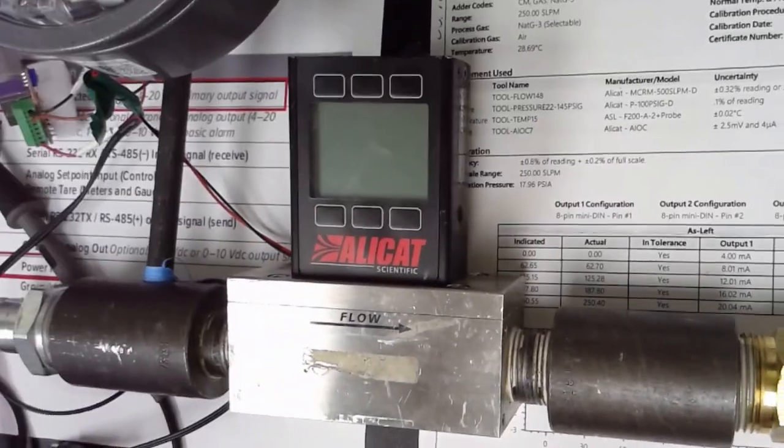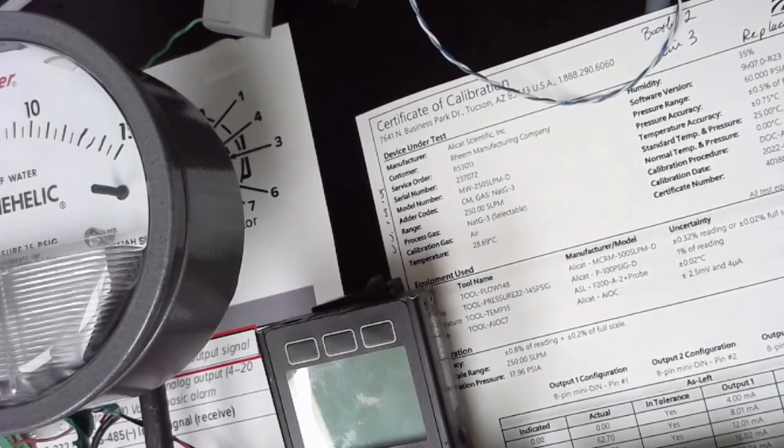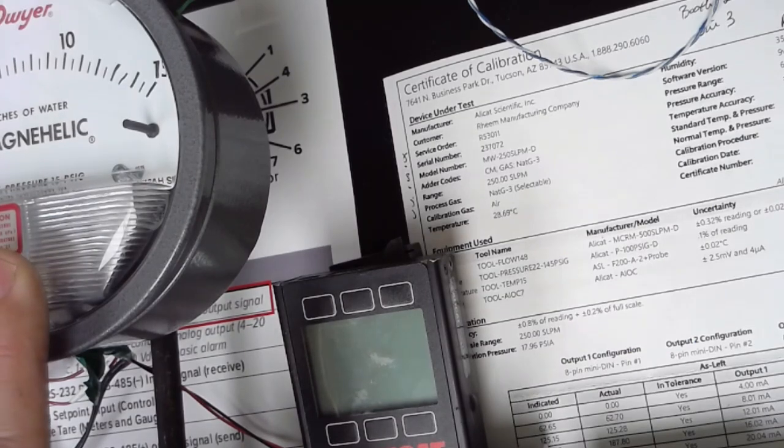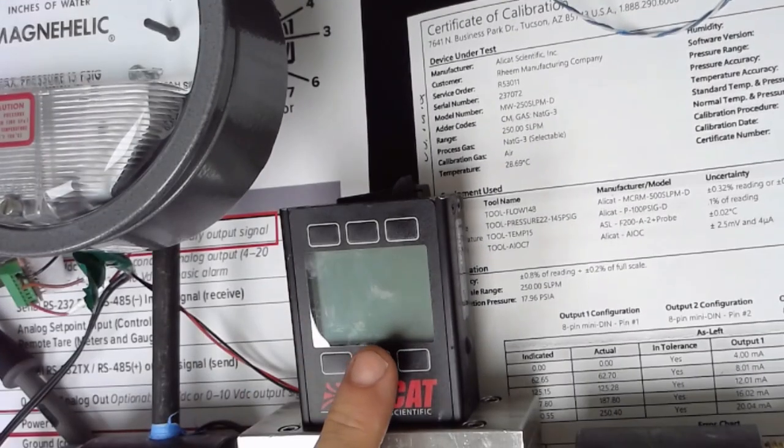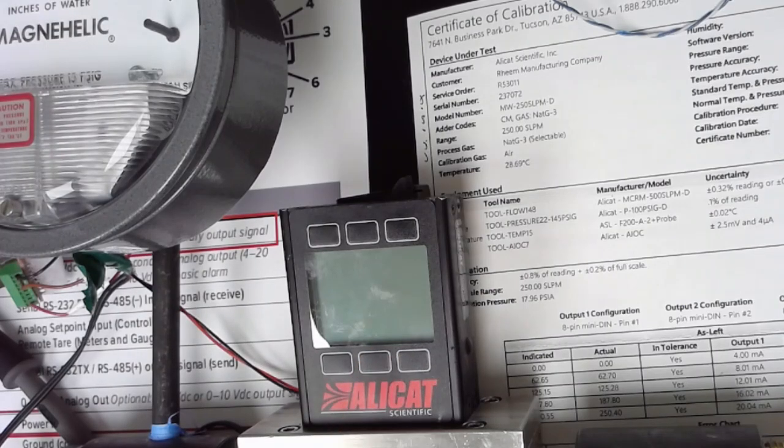It's installed on a quick connect that goes into the unit. This is a battery operated unit with the Magnehelic gauge. We can verify the Magnehelic pressure available to the unit is correct and we can actually read the flow. If the flow rate on this Alicat is over 10% different than the screen display, which comes from another Alicat, then we have an issue.